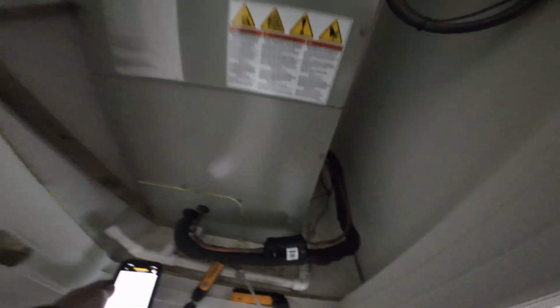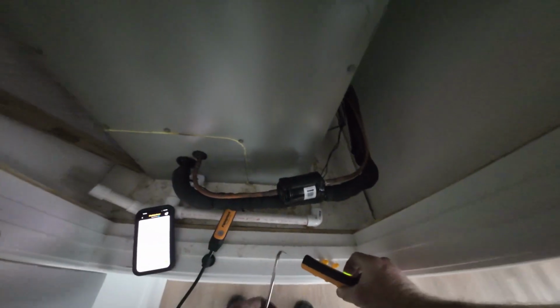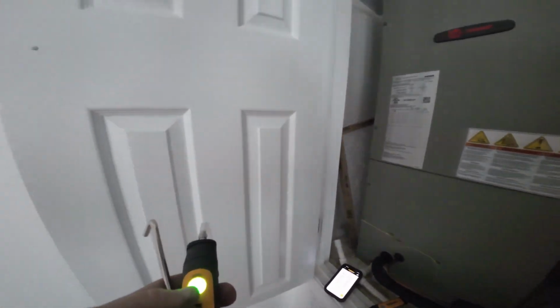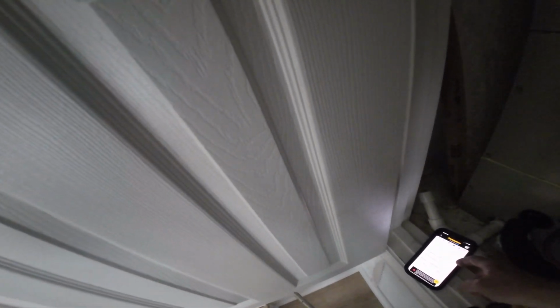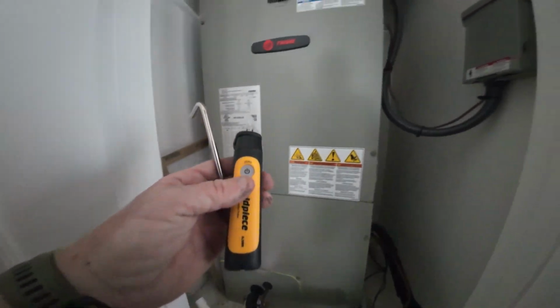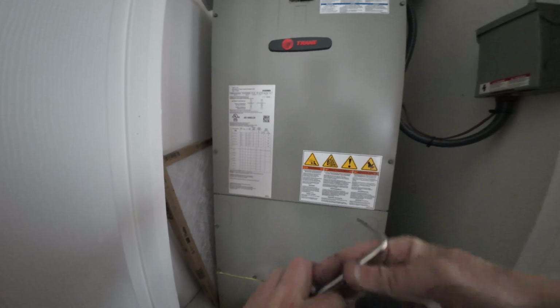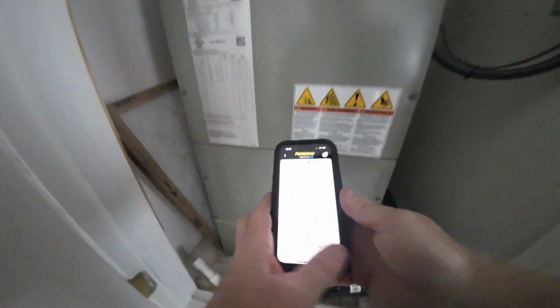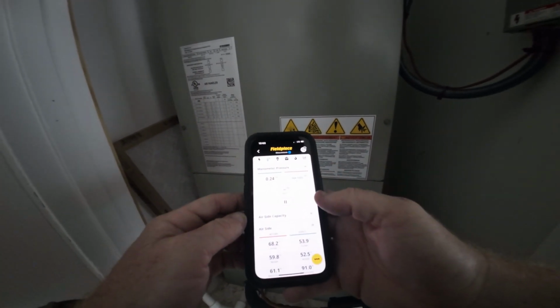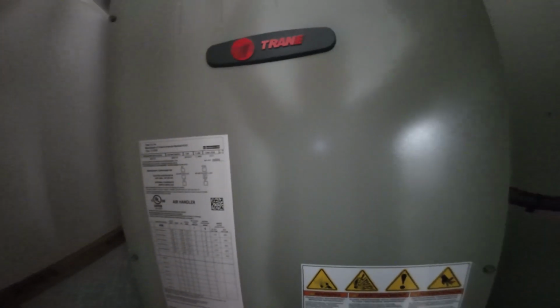So I'm going to double check static pressure. Go ahead and take this on. Zero it. To zero, you just click it once real quick to zero the static pressure. And then I'm going to use the same hole just to see what the static pressure is. So that supply static looks good. So we might need to go check refrigerant again.